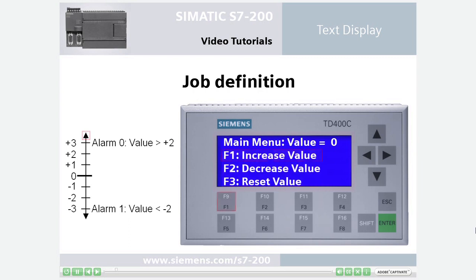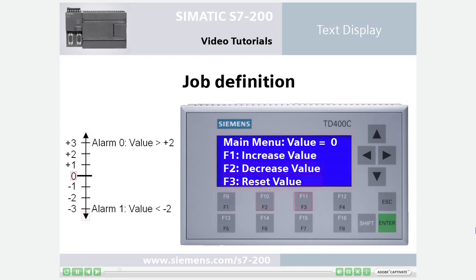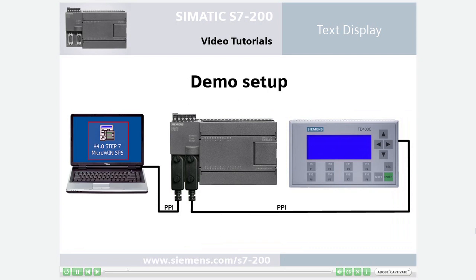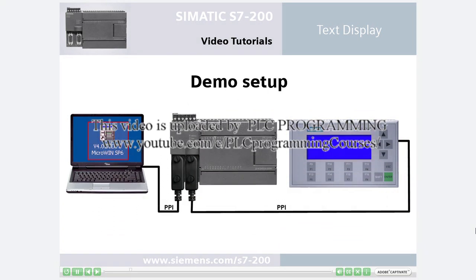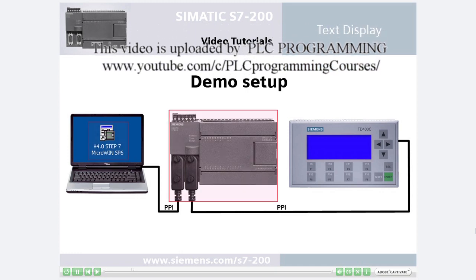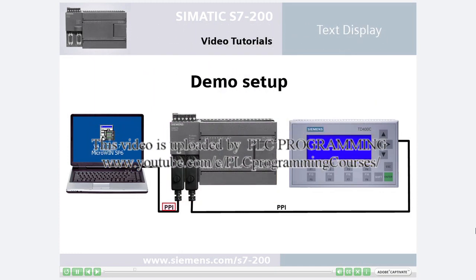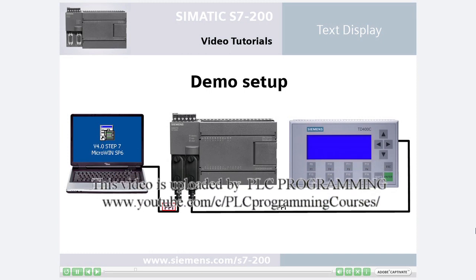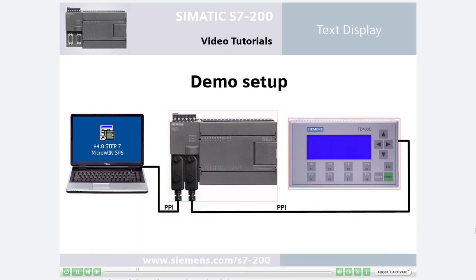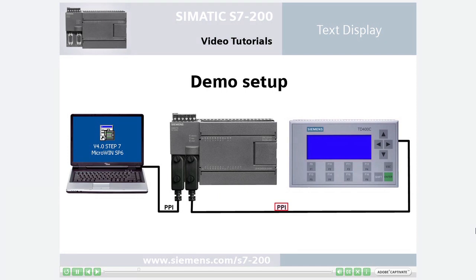The variable named value will be increased by pressing F1, decreased by pressing F2, and reset by pressing F3. If the value is greater than 2, alarm 0 will be displayed. If the value is less than negative 2, alarm 1 will be displayed. In step 7 microwin, the program code for the text display is generated with the aid of the text display wizard and is downloaded to the S7-200 controller via the PC PPI cable. The communication between the controller and the text display is also via PPI.